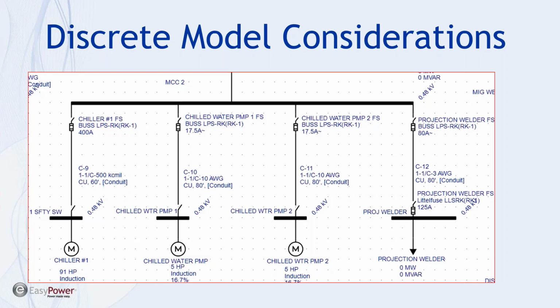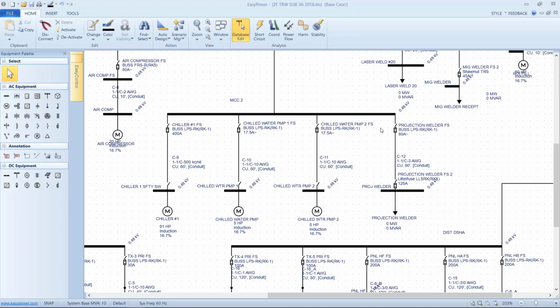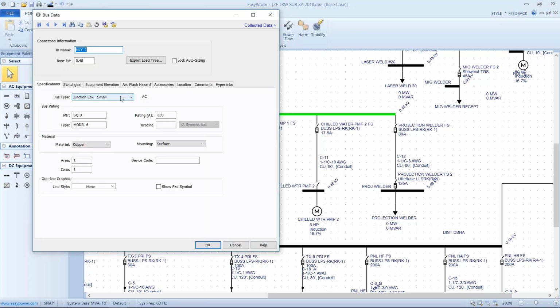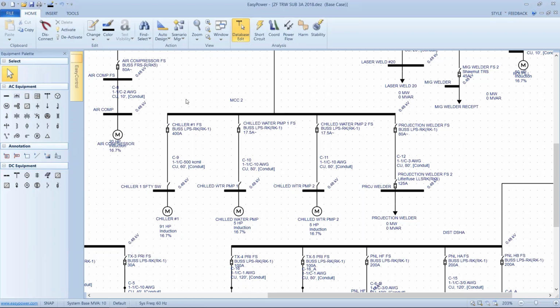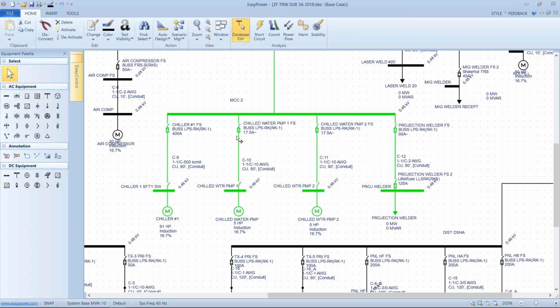So first we're going to look at this representation, if you will, in a one-line diagram. Here I've set up a discrete motor control center bus, and I've labeled the bus under the characteristics. It has been labeled as a junction box and correctly identified as a Square D Model 6, which is a motor control center, and a rating of 800 amps. Now the point I want to make is I'm going to isolate this particular motor control center and its buses.